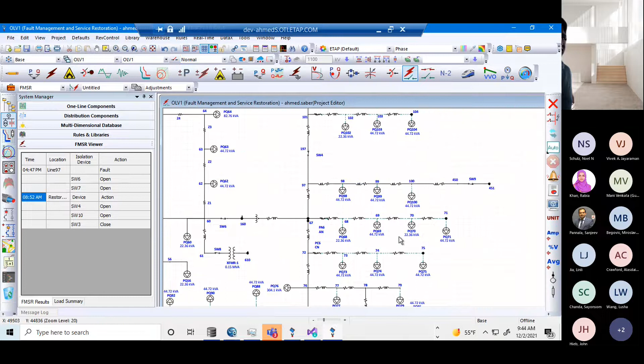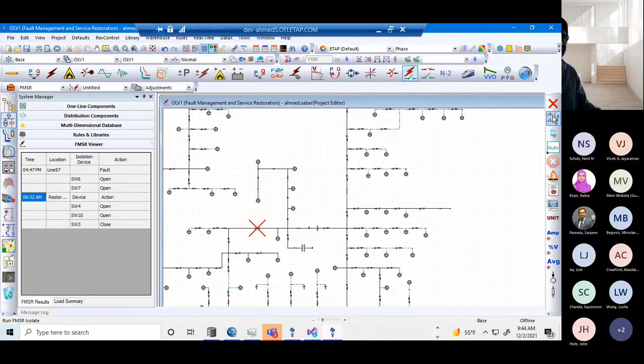If you run FLISR, let's say I have a fault here. In normal mode, we have a fault here. Then what happens? Which switch do I open, which do I close? First we need to open some switches to isolate the fault, and then restore service.